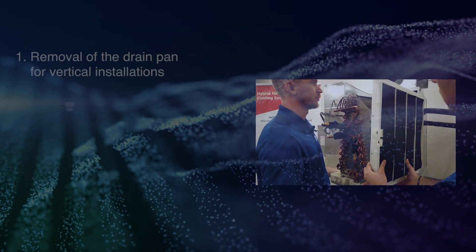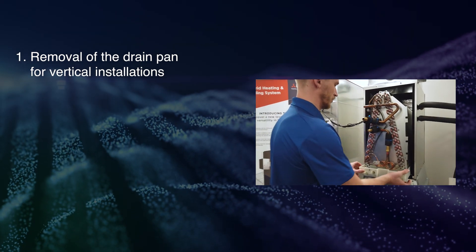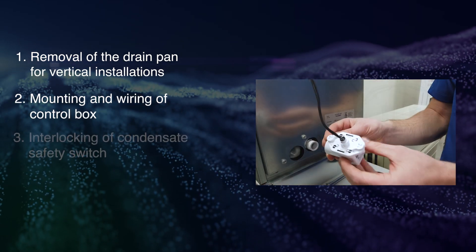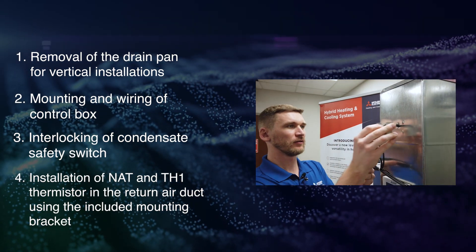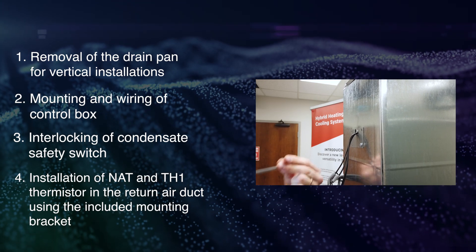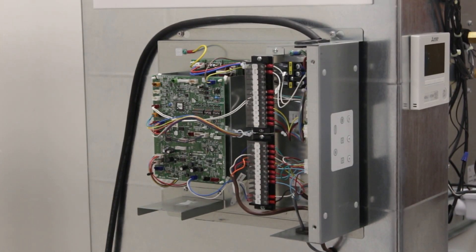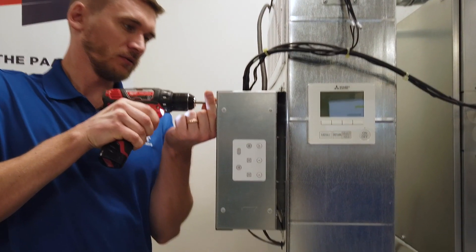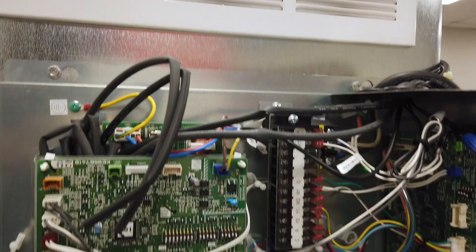A few things to know during installation: removal of the vertical drain pan for upflow installations, mounting and wiring of the control box, interlocking of the condensate safety switch, and installation of the NAT and TH1 thermistor in the return air duct using the included mounting bracket. The control panel must be placed inside the home within close proximity to the case coil. Power is supplied to outdoor terminals L1 and L2, while terminals S1, S2, and S3 are connected between the outdoor unit and control box.